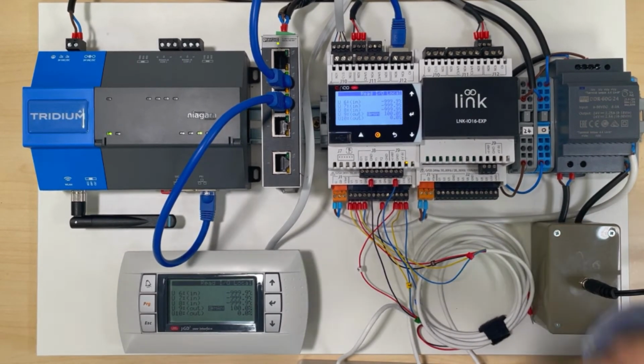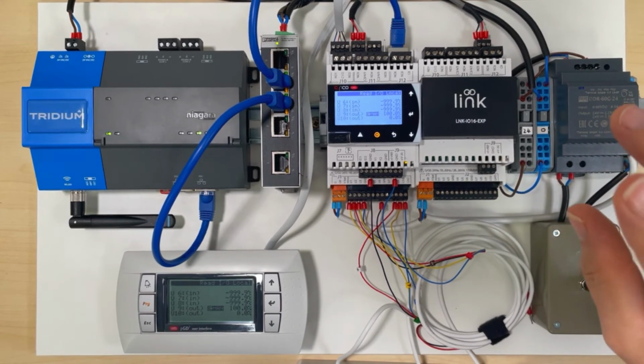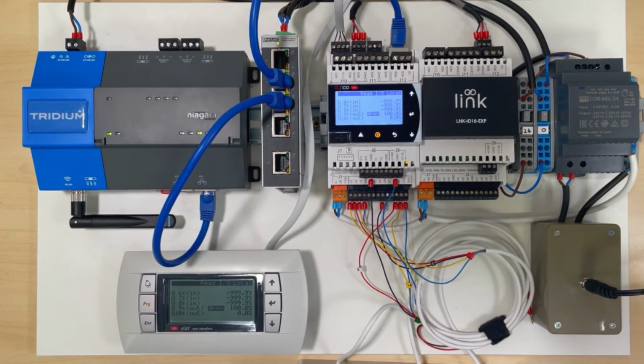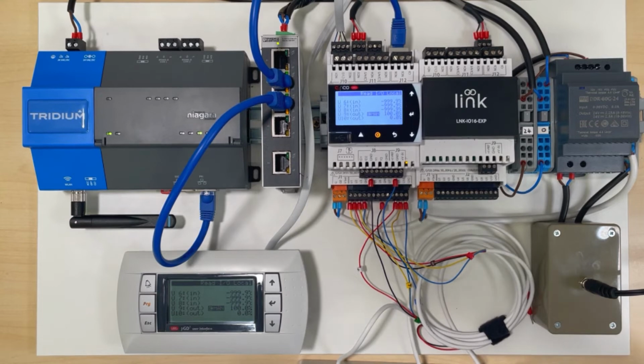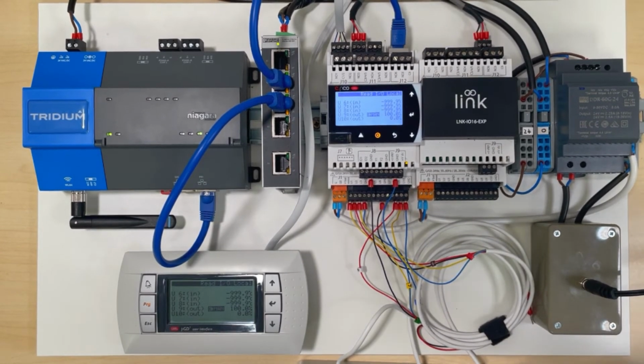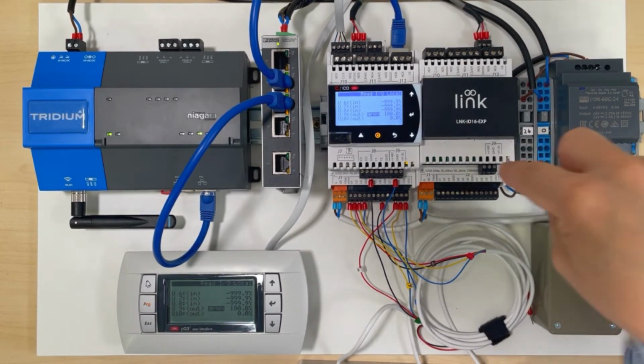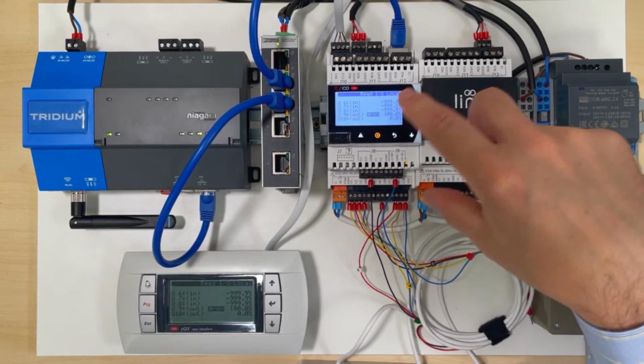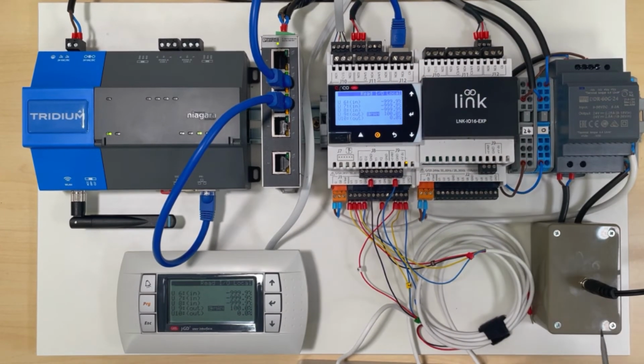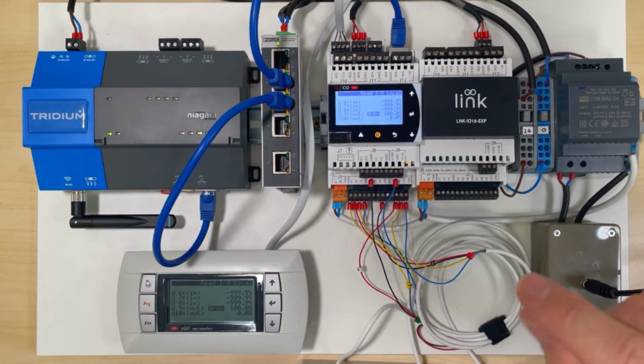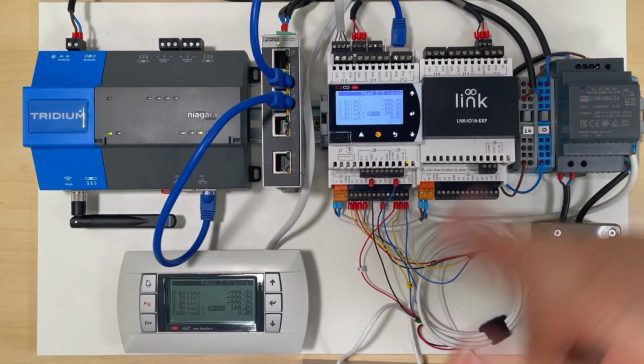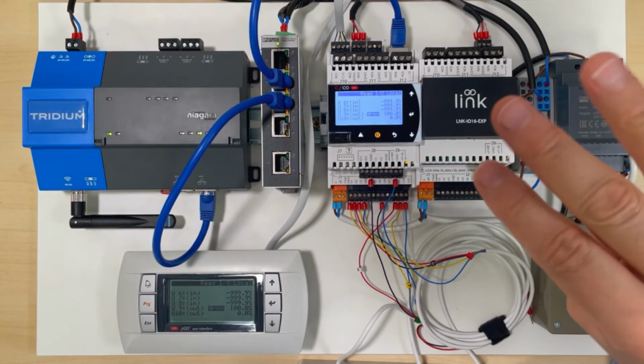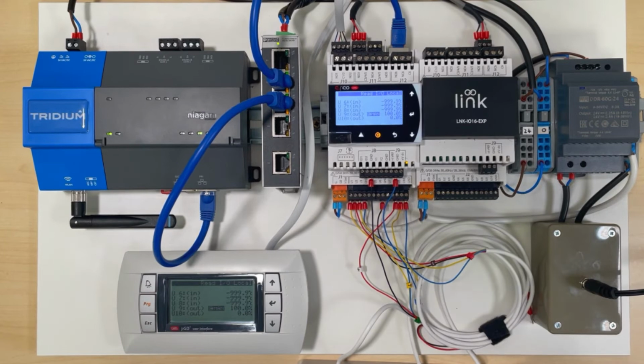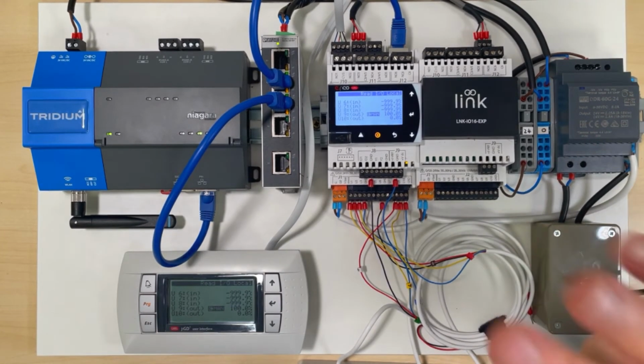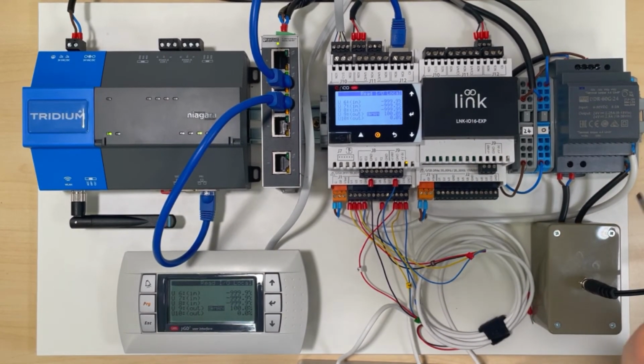If you've got any life safety functions, like looking at a fire alarm input and positioning some smoke dampers, that will take priority over the watchdog, because the function can still control and read the input. After that, manual control will trump everything and take priority. So you've got to consider that when creating your strategy, especially in critical life safety scenarios.